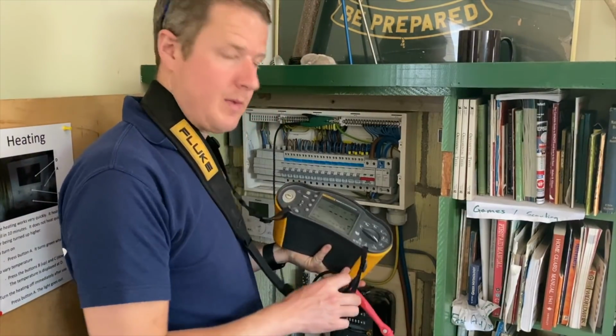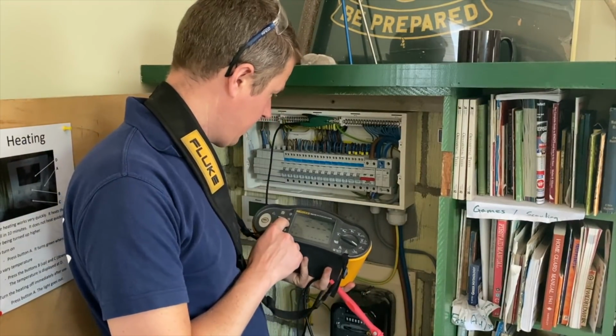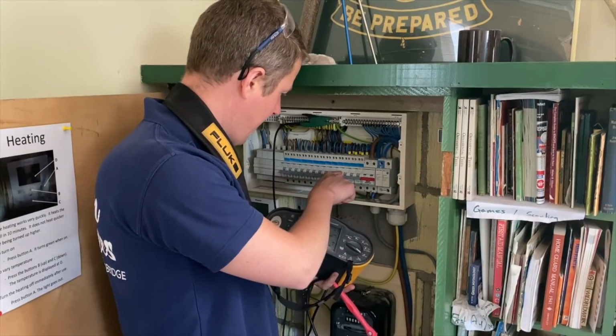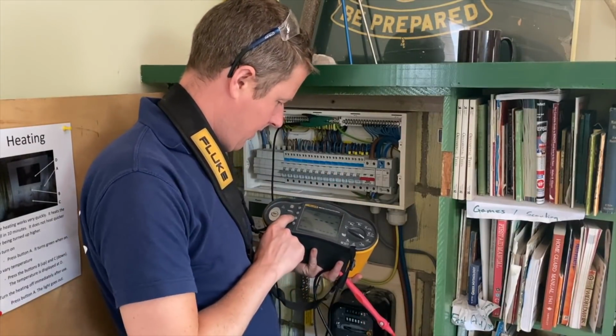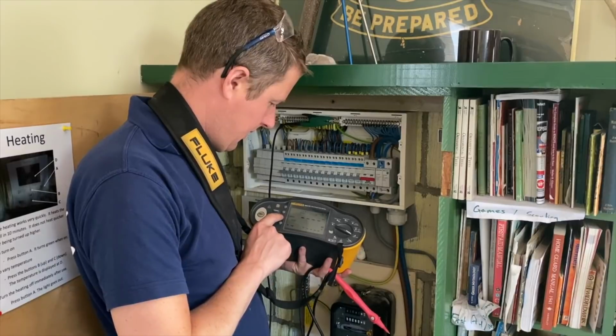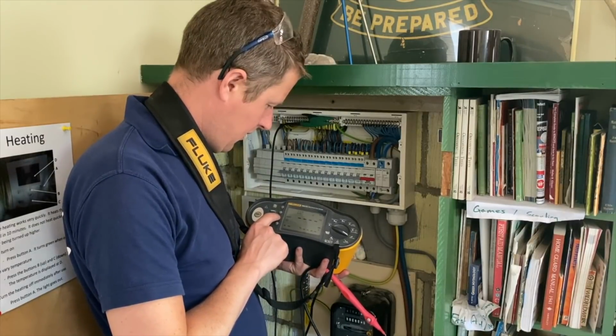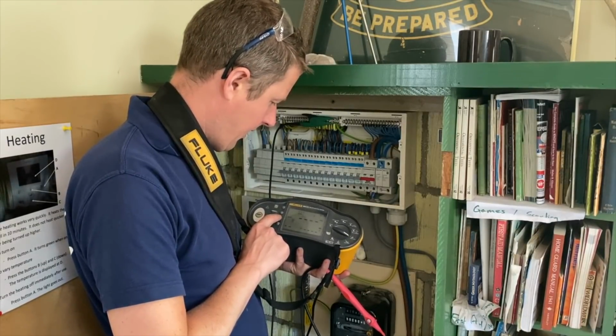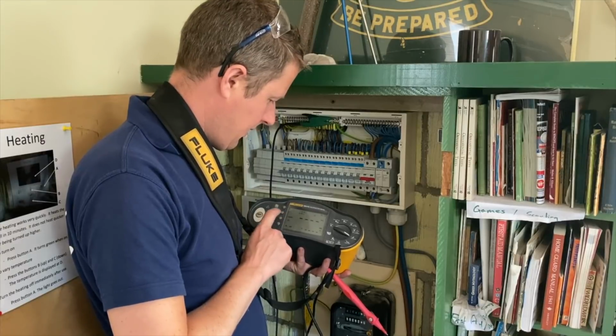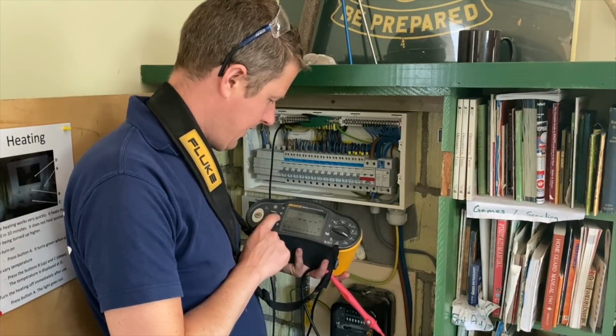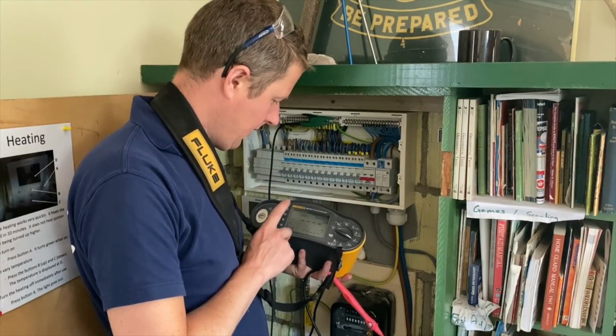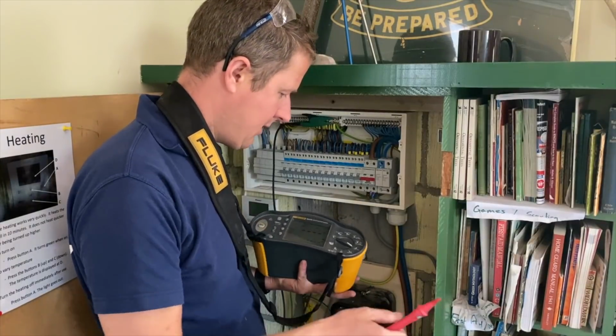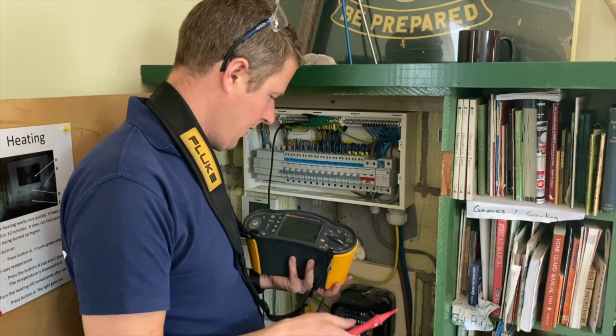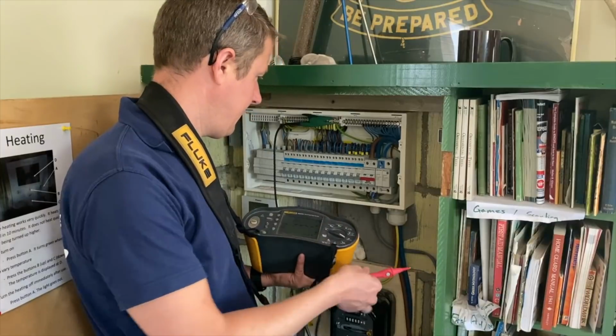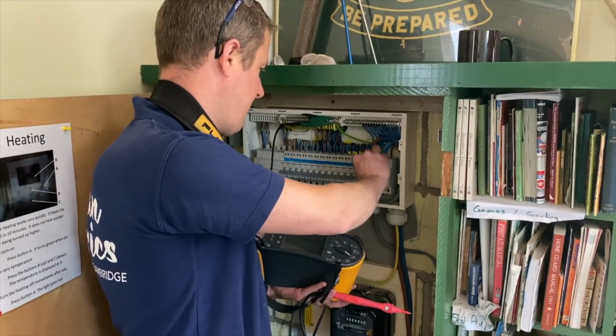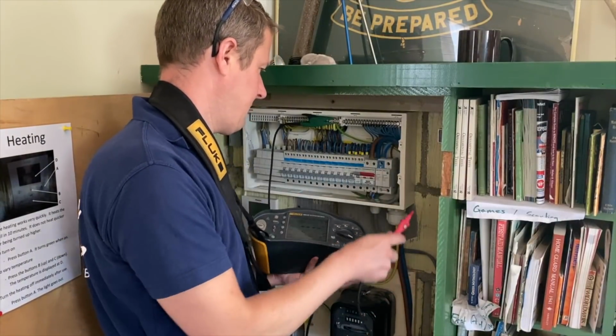this Fluke tester has an auto test function, which is quite good. Now these are type AC RCDs. No, sorry, type A RCDs. So they test both AC and DC fault current. So I'm going to have to do 2 sets of tests on each of these RCDs. So I'll select it to auto setting, turn the main switch on, and then turn the first circuit breaker on.